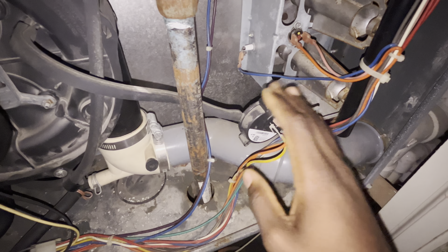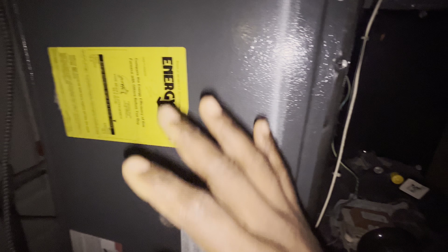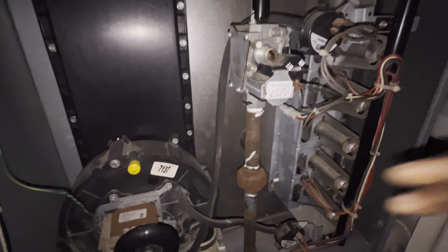Secondly, actually there's 2 of them on this furnace. There's another one up here. If this motor doesn't make the right pressure, if there's a buildup of, say, condensation in here, we'll get one of these tripping. It's a different flash code. Secondly, if the blower motor wasn't moving enough air, say for example a dirty filter, I've seen it where that caused this limit to trip in a different type of furnace. But we have a chamber limit right here that didn't trip. That would be a different flash code.